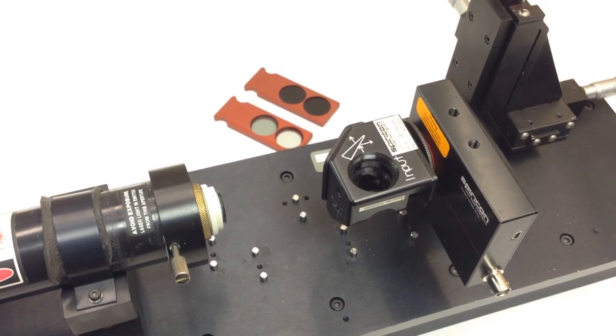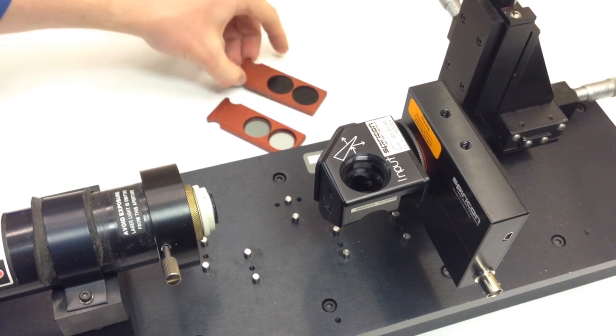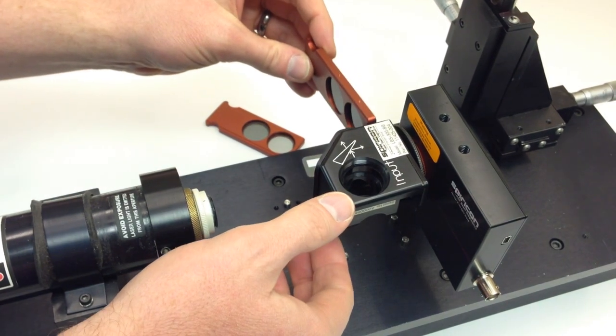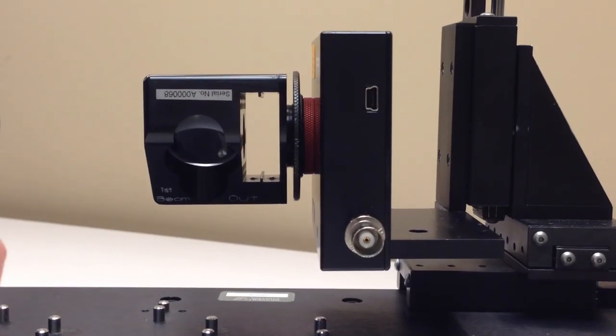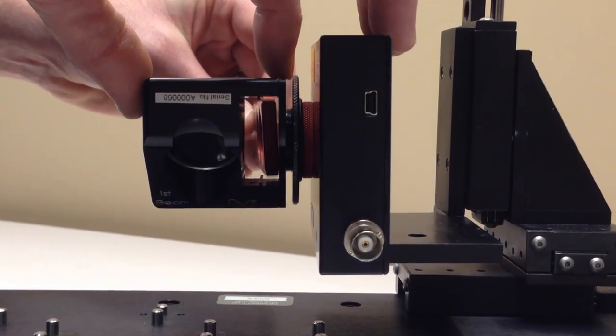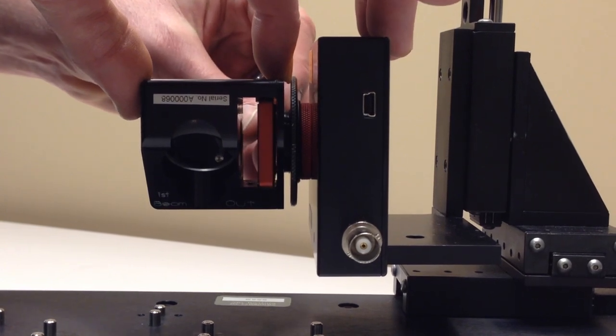But another good way to adjust the beam attenuation is also these sliders that we provide with the LBS 300. You can simply slide them in. They have a couple of different neutral density values on each side, and you can just slide this in to adjust the attenuation level.